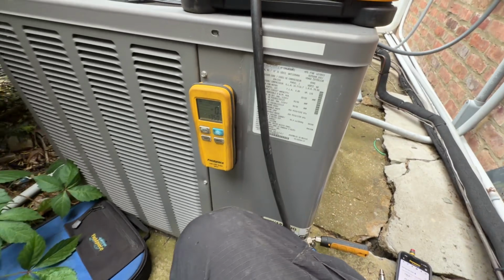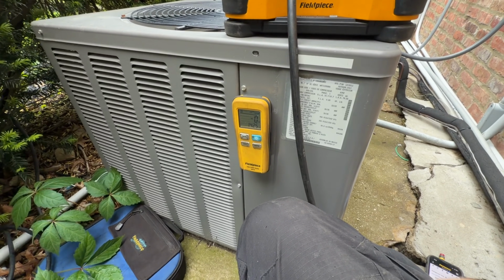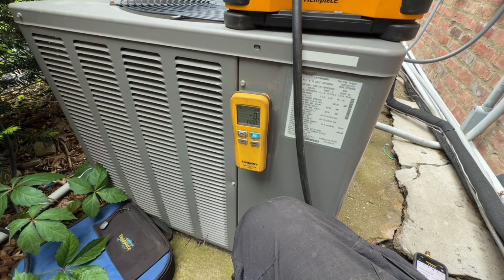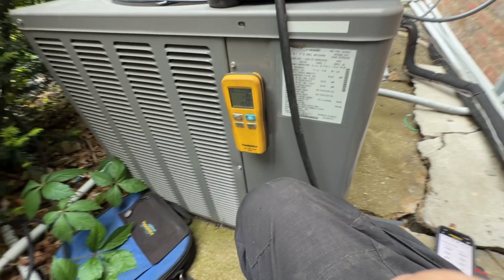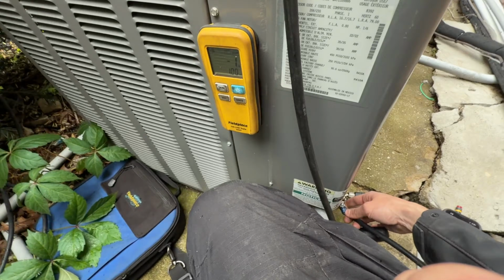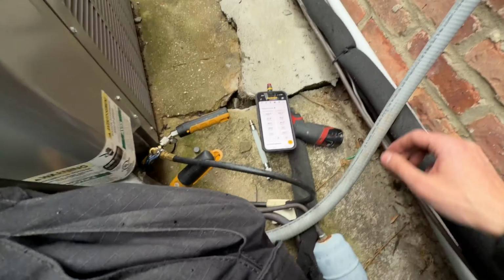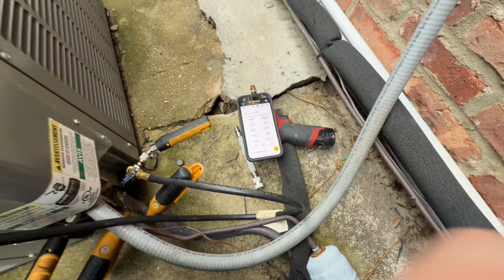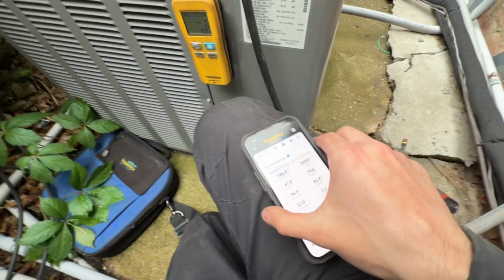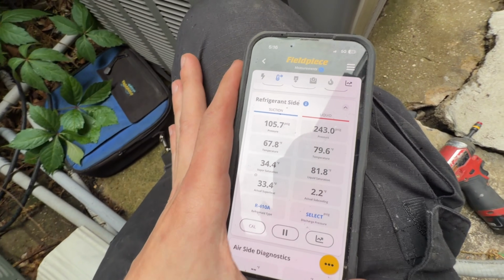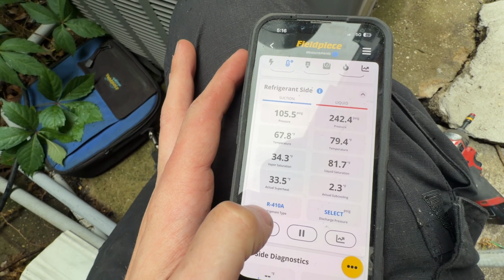So far, 13, 14 ounces, 15 ounces, 16 ounces, so that's a pound. And we'll just see what happens there. We'll let the pressure stabilize. We want to bring our subcooling up and our superheat down, which is what adding refrigerant will do.